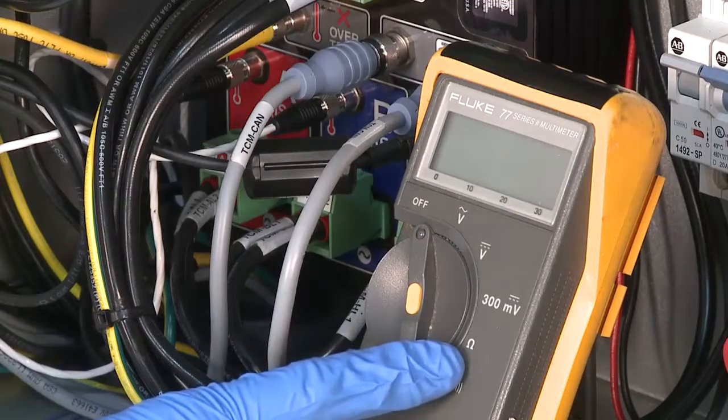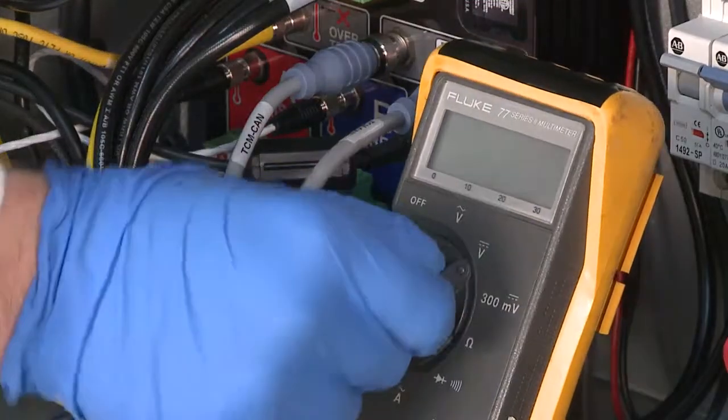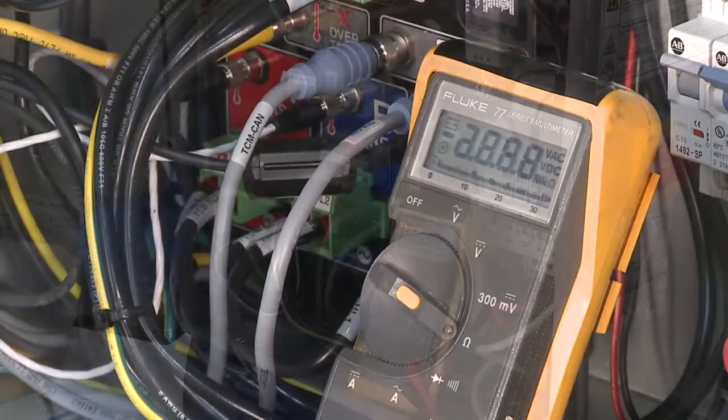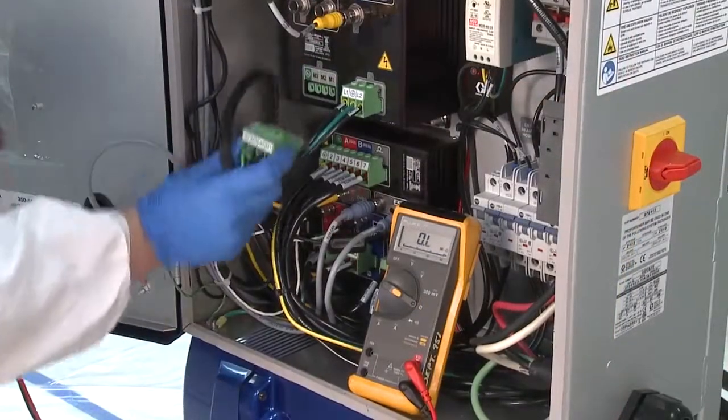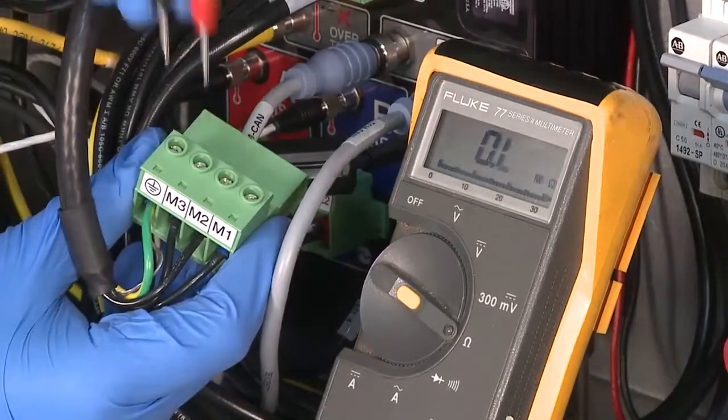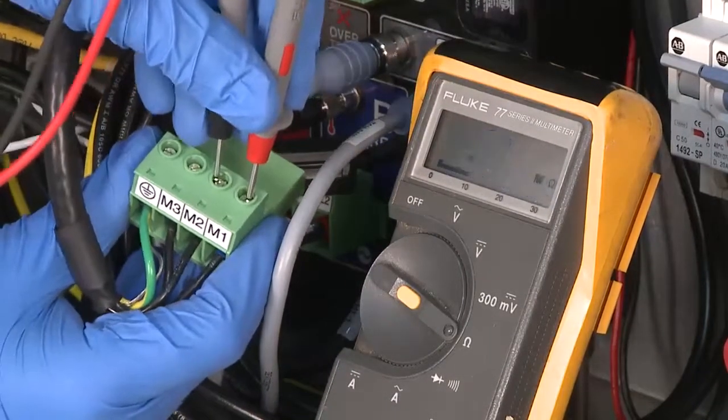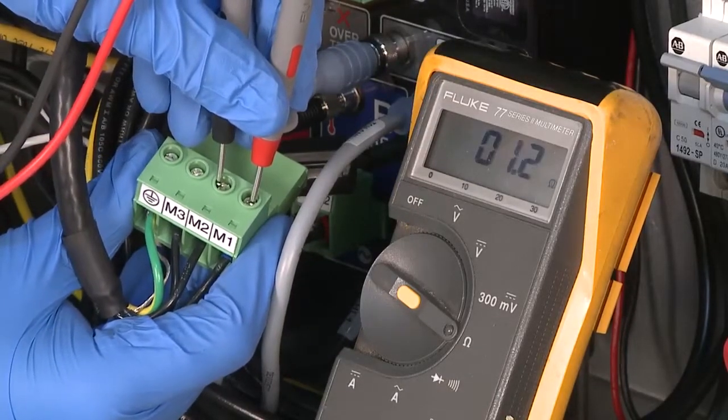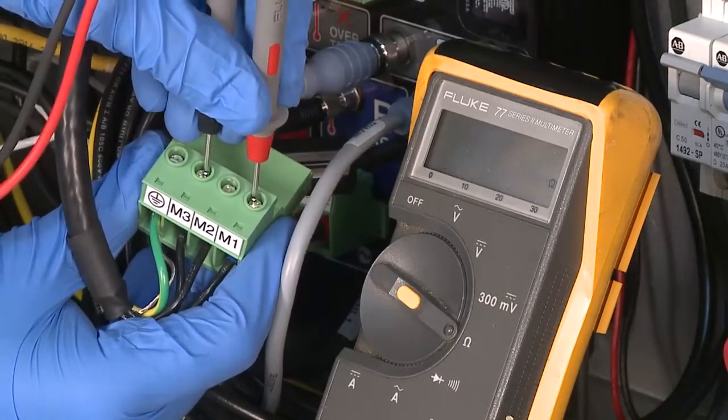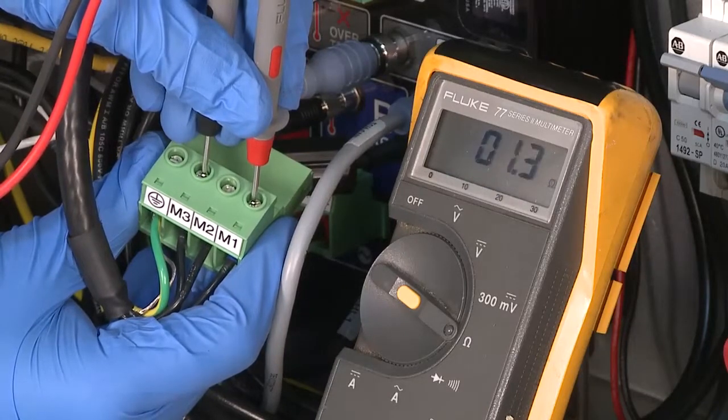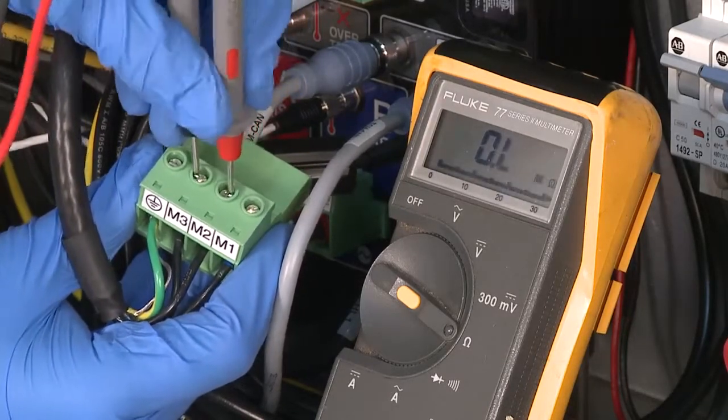Measure resistance at the motor power connector. Disconnect motor cable from MCM port 15. Readings must be less than 8 ohms resistance between each pair of motor power leads: M1 to M2, M1 to M3, and M2 to M3.